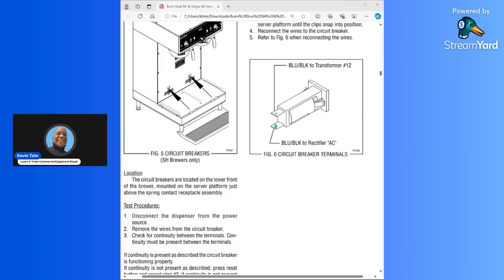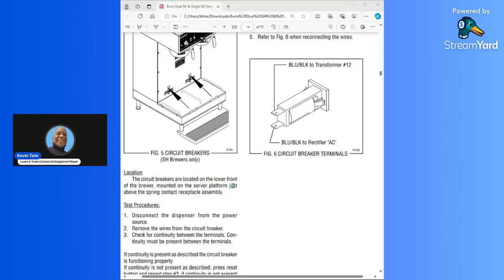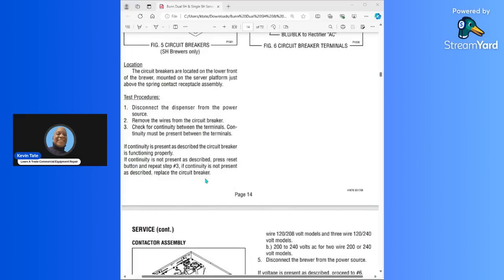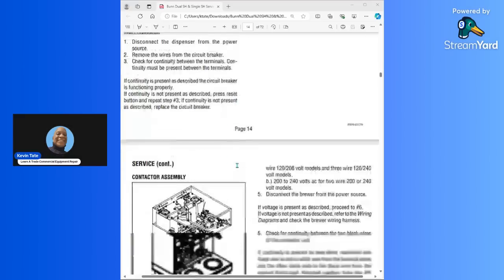And if you don't have continuity, then you could reset. You can just press in the front button on that. It's right on the front section here. Just push that in and it should reset. If it doesn't reset, then you would have to replace the circuit breaker.